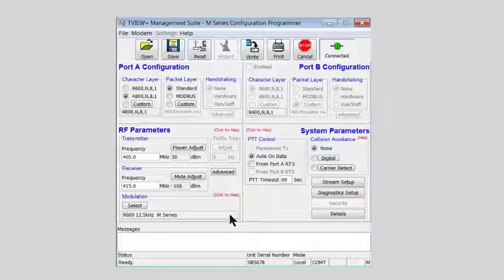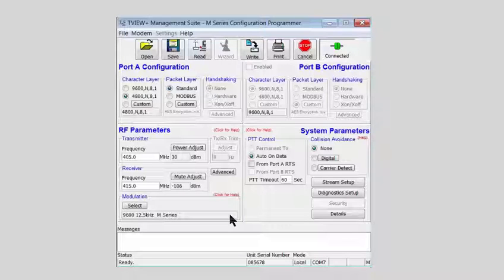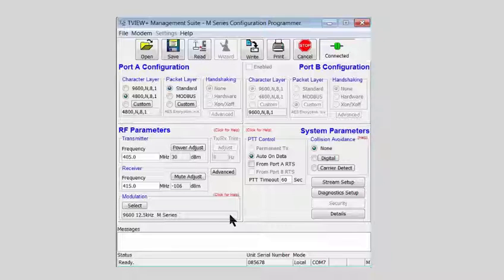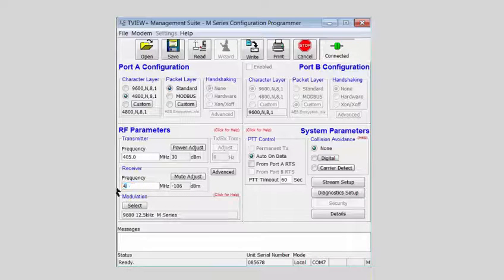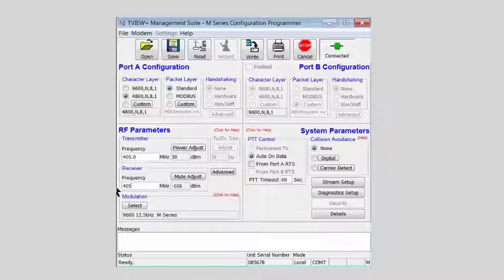Serial port A may be configured for character layer and packet layer settings, as required by the protocol to be used. Port B here is disabled, as the M-Series radio has only one user port. The discontinued E-Series radio does, however, have two ports. The transmit and receive frequencies must both be set to the same channel for simplex mode. We will use 405 MHz in this demonstration.